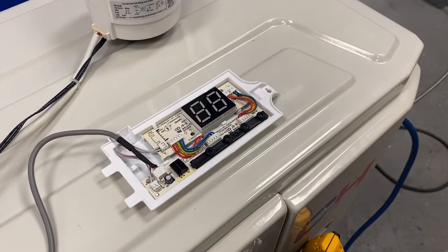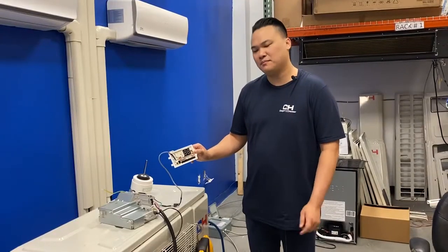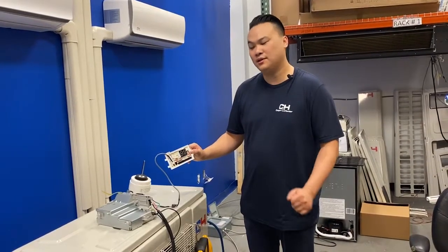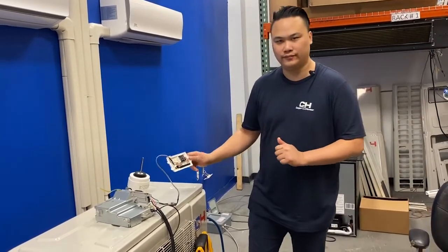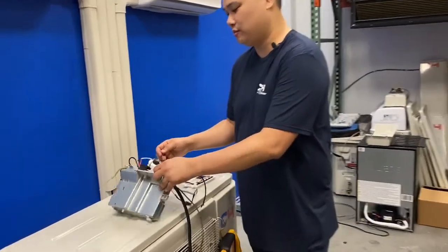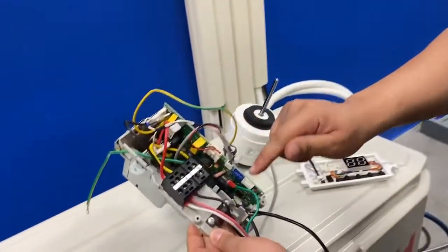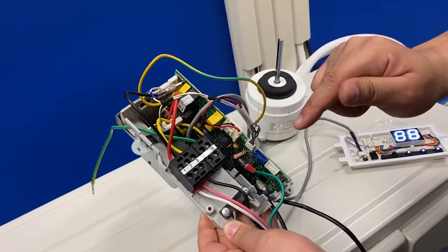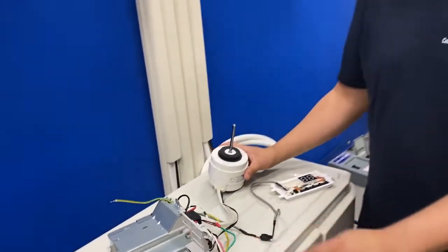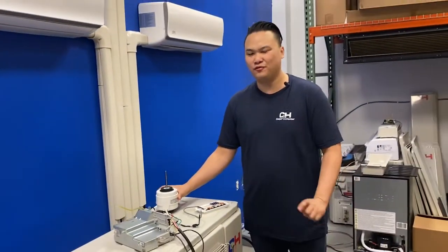If your indoor unit is flashing 88, it could be one of two things. It could be the main control board or the fan motor. In the main control board, you would check at the terminal power and resistance. And if it's the fan motor, it could either be jammed or a faulty motor.